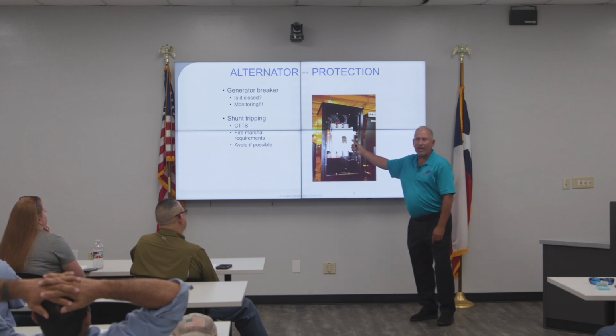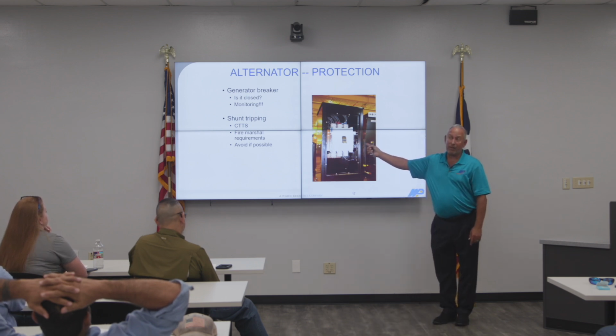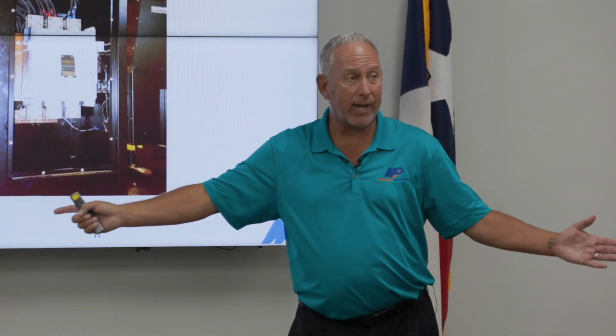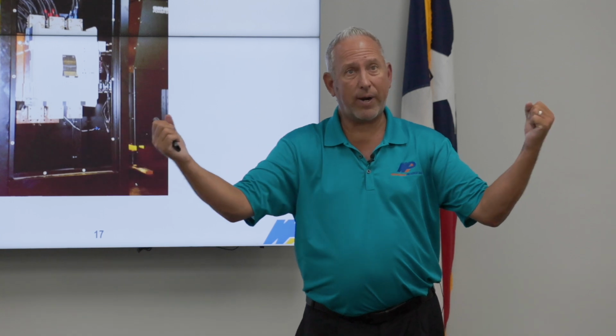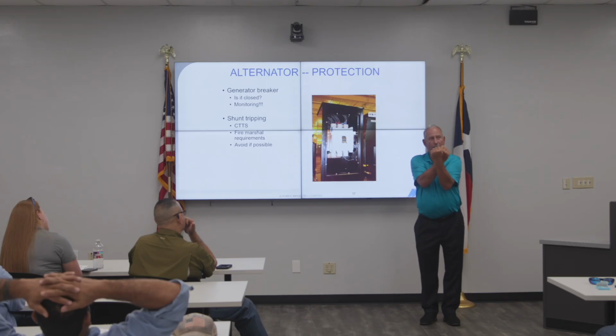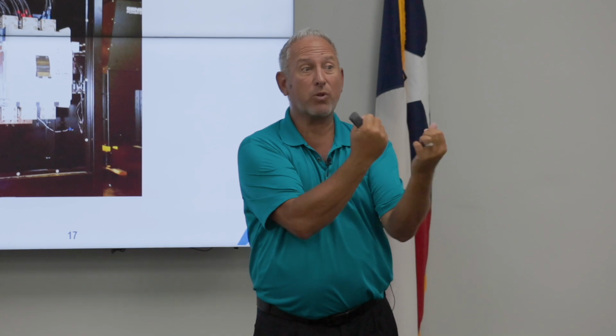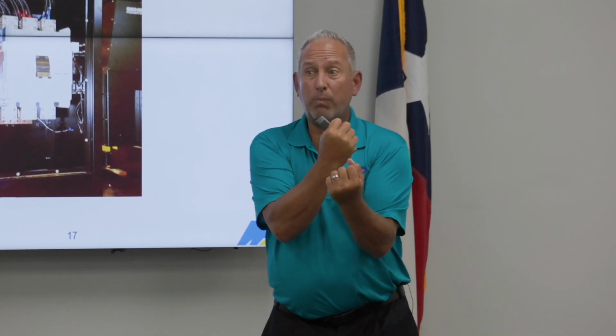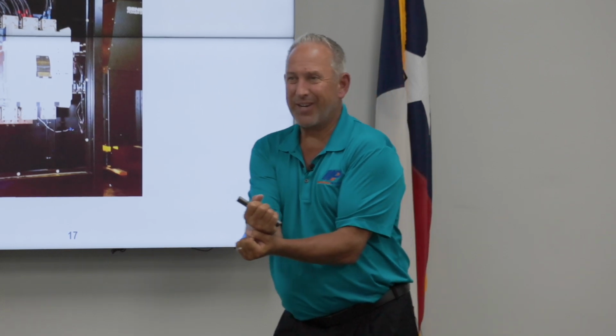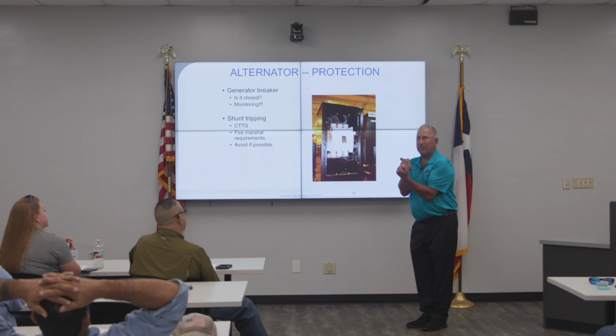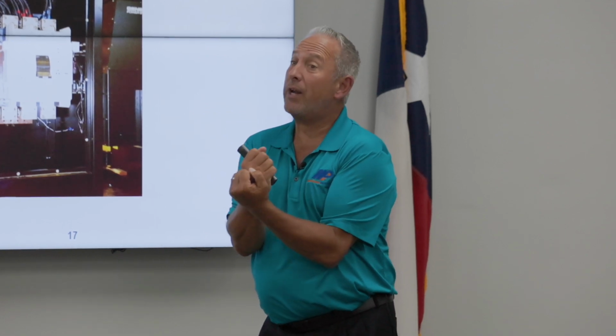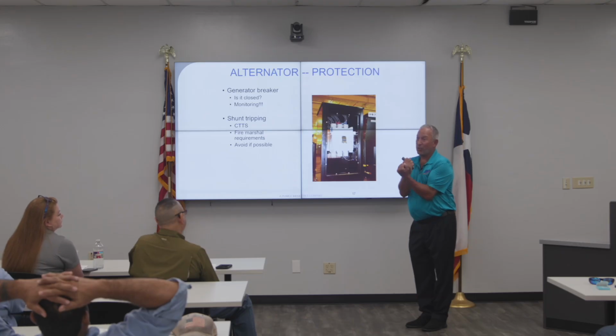If you have a closed transition transfer switch, you avoid that second hit. So what that switch can do is that switch goes, okay, utility's back. I'm going to wait till the generator and the utility align with each other. And once they've aligned with each other, I'm going to close on top of it and then let go. So that way there's no interruption coming back. So you have to ask the utility company if you're allowed to do this in your area. Most utility companies, they say yes, they say no. But they do say that if you are going to do that, you cannot be tied to me longer than 100 milliseconds. So once you're on, tick-tock, you've got 100 milliseconds to go.